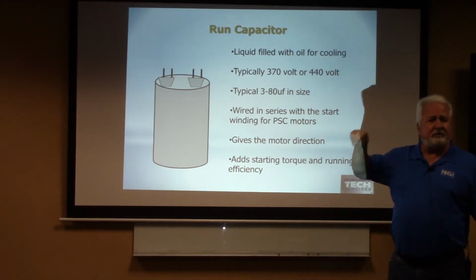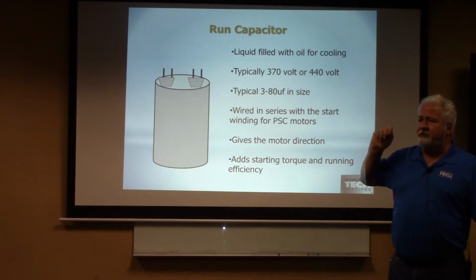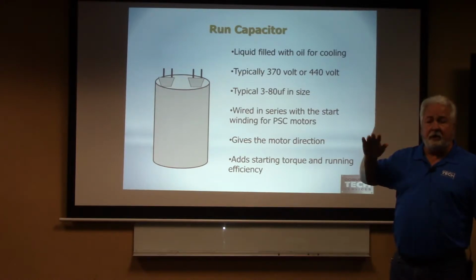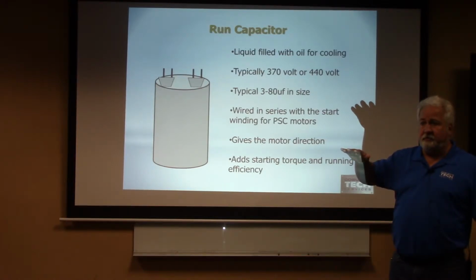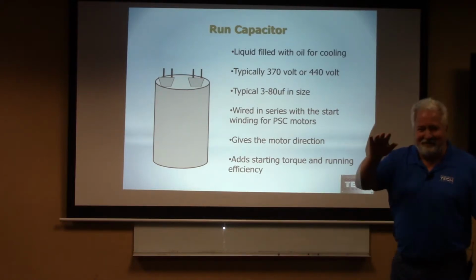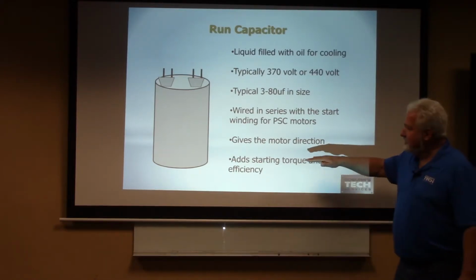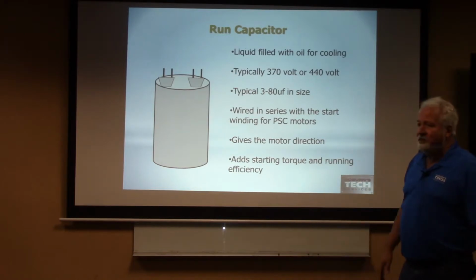Ever disconnected the run capacitor? What does the motor do? Right? Doesn't go in any direction. You know why it hums? Because it doesn't know the words. All right. It adds starting torque and running efficiency.